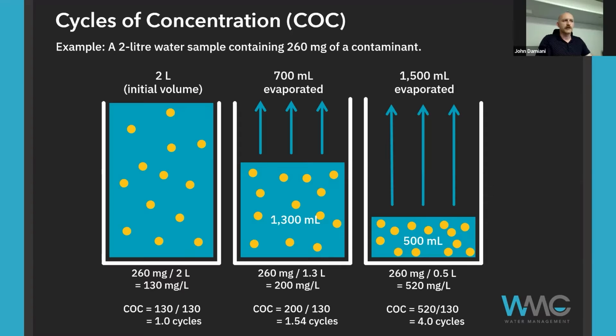And the way we design water treatment is we need to consider this, and we need to compare all these cycles against the maximums that are established either by the manufacturer of the cooling tower or just industry knowledge, the best practices of what we know that we can run at. Also considering, again, the temperatures that are in that system and the equipment that it's exposed to, whether we've got chillers involved or plate and frame heat exchangers or whatever it might be, that's all going to affect what we can cycle. So we can calculate cycles based on total dissolved solids or on individual parameters like calcium or total hardness or chlorides, for example. All these things need to be looked at in order to design the system.